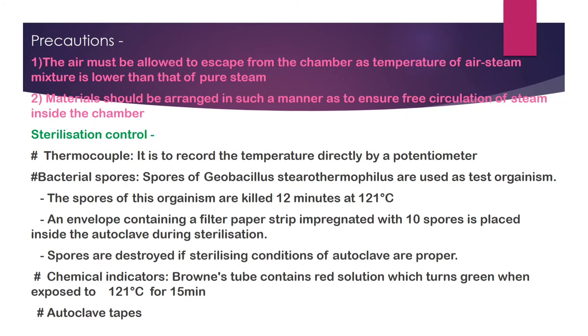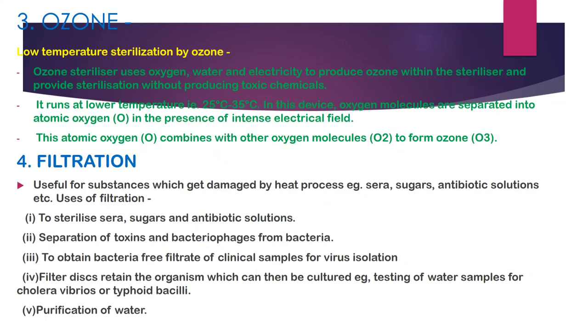Chemical indicators: Browne's tube contains a red solution which turns green when exposed to 121°C for 15 minutes. Autoclave tape is also used. Ozone sterilization uses a low-temperature ozone sterilizer that generates ozone from oxygen, water, and electricity, providing sterilization without producing toxic chemicals. It runs at 25°C to 35°C.